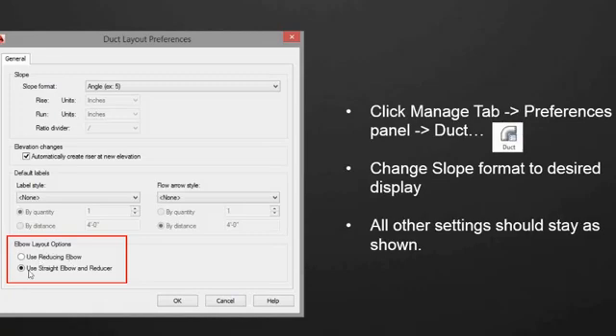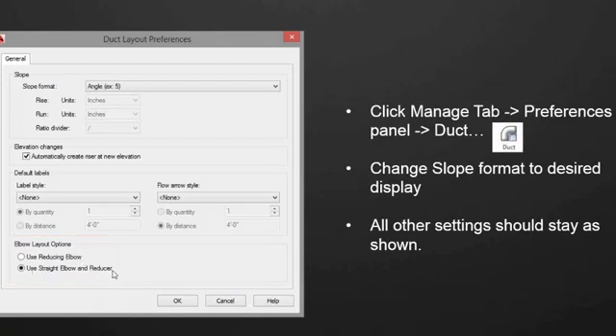Elbow layout options. This needs to be set to use straight elbow and reducer. Our duct currently does not work with this use reducing elbow option, so this is the option that you need to use. And if you want to have a change elbow in there, you need to change it after you've placed your duct.